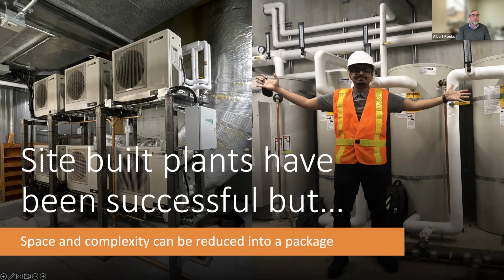So we've got a lot of site plants that have been built, and they really have been successful, but we can do better, right? If you look at that plant, left-hand side is 1075 West Georgia, that big tower, and that rack system is in the upper mechanical room. It's a hot room, so it's a great place to place those heat pumps. They'll just soak up that heat, turn it into heat in water pipes, and then give it to storage, which is placed elsewhere in the room. In an existing building, that's a great way to do it because you've got to cart all this stuff up, somehow get it into the room, and then assemble it on site.